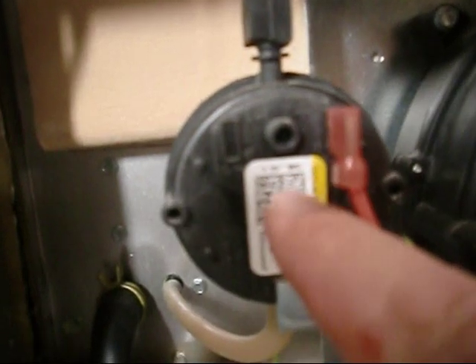And for your furnace to fire, the pressure switch here proves that your vent's open here, and you don't have any obstructions in it. And once this fan reaches a certain speed, this particular pressure switch here is 1.15 inches water column.